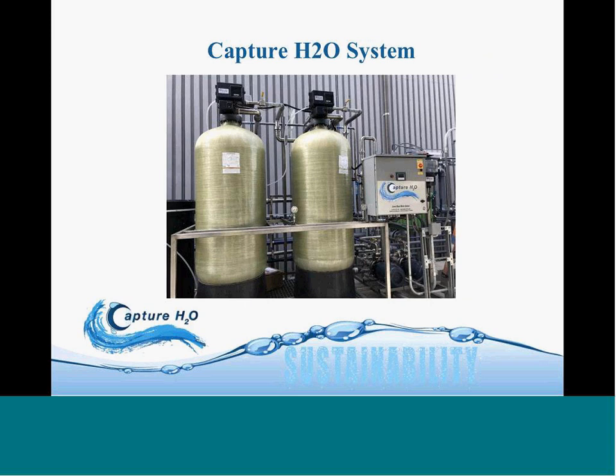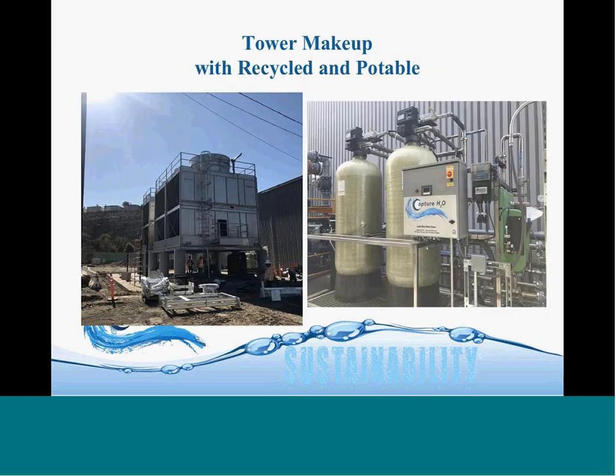This particular system is our skid-mounted version. Everything's in stainless steel. We had the system, the pumps, and the control panel all pre-assembled and shipped in. To the right of this picture, there's a storage tank where the water blends in. This system can handle up to 4 different water sources into that tank, repressurize the water, go through the pre-treatment system, and send it into the cooling tower. So we can customize the ratio of the waters to maximize the use of the free or least expensive water and minimize any potable water usage.